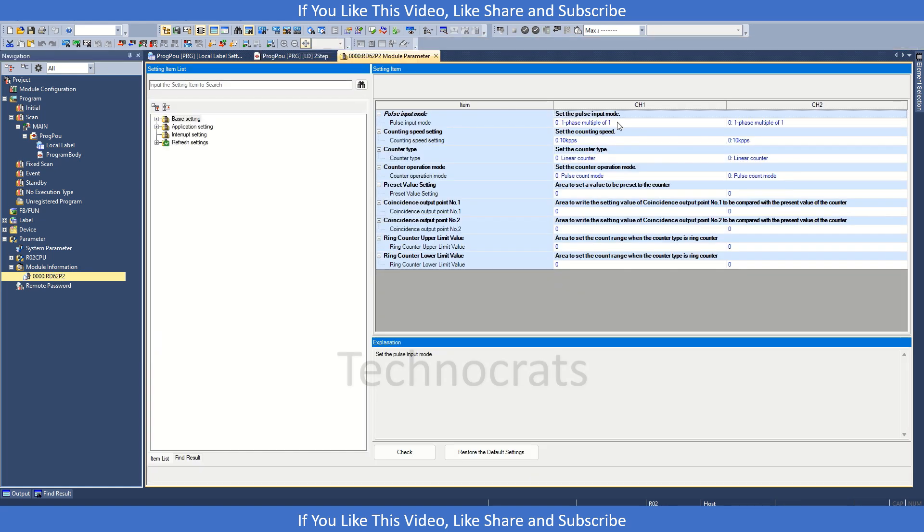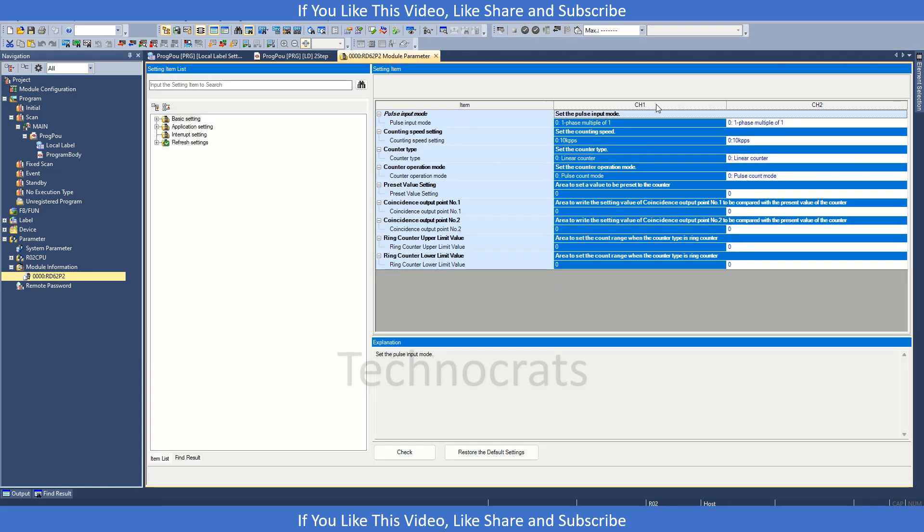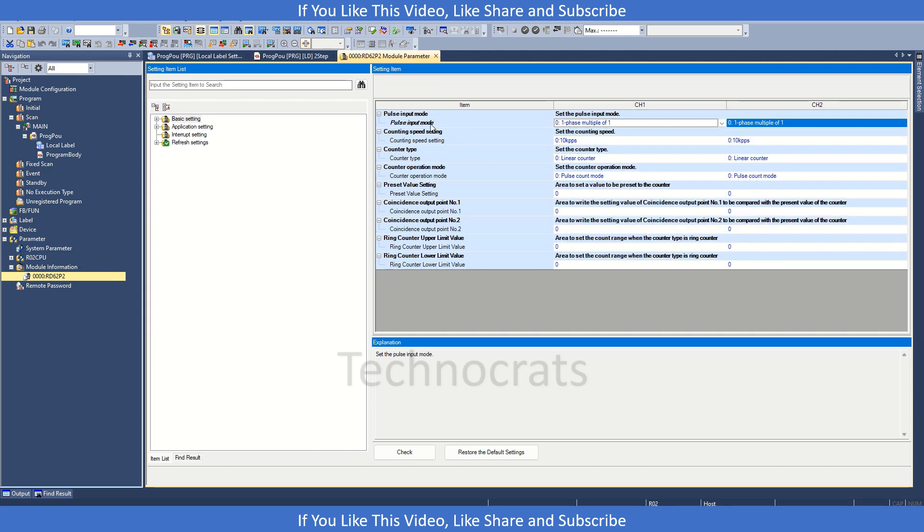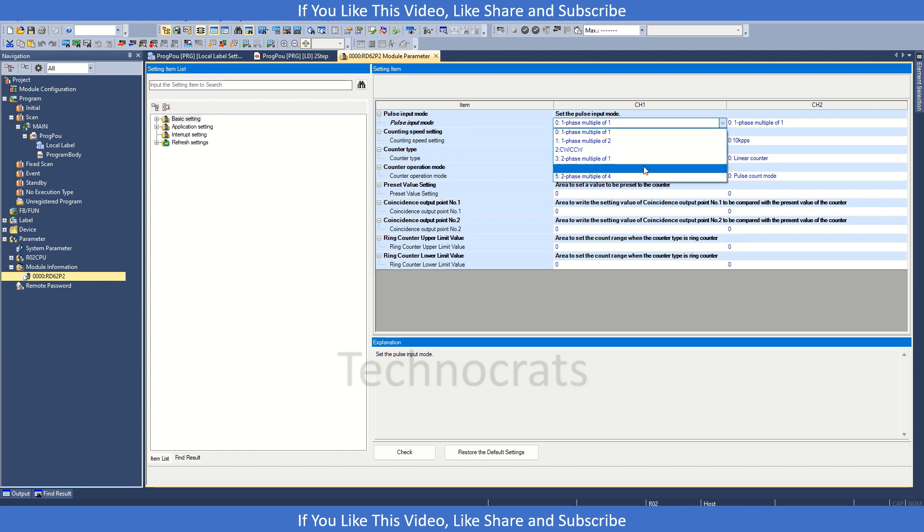Here we get two channels, Channel 1 and Channel 2. So the first setting we have is pulse input mode.